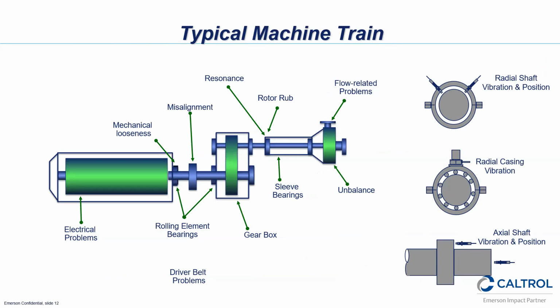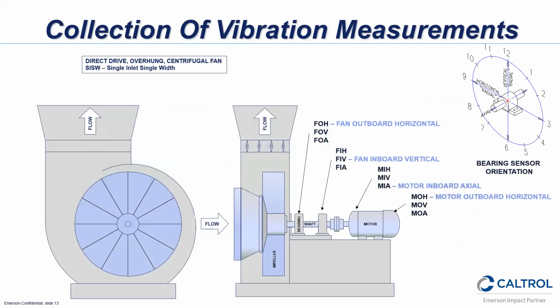This is a typical motor train, basically a motor, a gearbox, and a pump. It shows the different points where we'll collect data on these units and the types of problems you'll see from those points, and the positioning on how we collect data on these assets. This is a typical fan unit, which shows, if any of you are using vibration analysis or getting reports, you'll become familiar with some of the technology and the acronyms that we use for the different fan positioning points that we collect the data on.